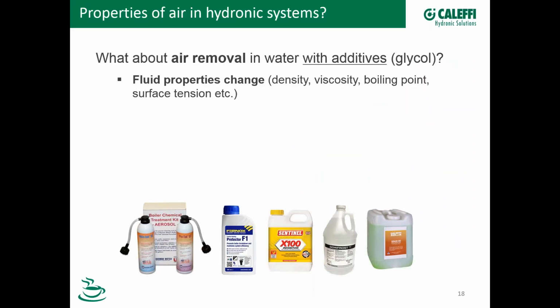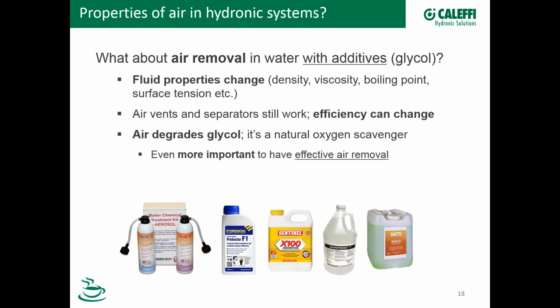Now, what about if we have chemicals or additives or glycol? What changes? What things happen here? Well, first of all the fluid properties change. So the density, the viscosity, the boiling point, and these properties change. So as a result, the air vents and separators will still work, but the efficiency can change. In other words, it might be harder to remove that air because we have different properties of the fluid. And because there's oxygen and air in the system, we know that that degrades glycol. In other words, it breaks down the glycol. So it's even more important to make sure that we have effective air removal when we have additives and chemicals.